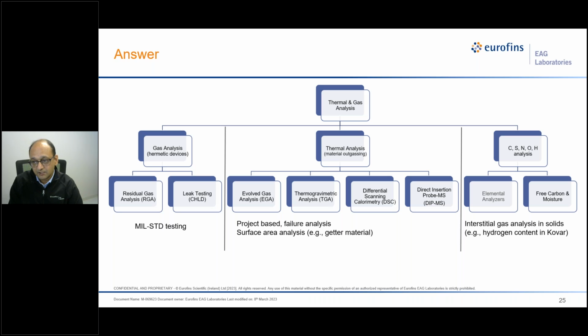But here at Syracuse, the thermal and gas analysis division can be subdivided into 3 different parts: gas analysis for hermetic devices, where we discussed today this residual gas analysis. We also have a leak testing capability where we can look at the very fine leak into the microelectronic devices. In the order of 10 to the power minus 10, minus 11, minus 12 range of leak can be tested using CHLD, which stands for cumulative helium leak detection.